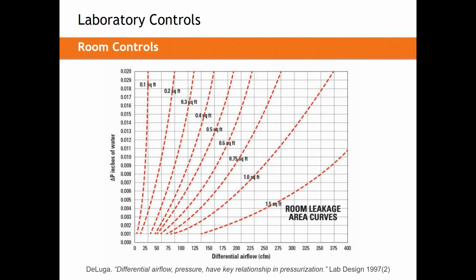As mechanical designers, we won't have information this good. We'll generally know where on these red curves we sit, but we won't know exactly where. So sometimes we'll see airflow balance plans that show 100 CFM of offset to hit minus 0.01 with an air change rate of 6 air changes, and we'll see that needing to be exactly hit upon. That's in the contract documents, that we must achieve this pressurization at this offset. I'm here to tell you that that's not our job. Our job is to make sure the balancing team has the authority and ability to hit 0.01 inches. That might happen at 1 CFM of offset, that might happen at 1,000 CFM of offset. Designing a mechanical system to give you that range of airflow difference is nearly impossible. But we can provide, let's say, between 50 and 200 CFM of offset to the balance teams to make this happen. That is our job.